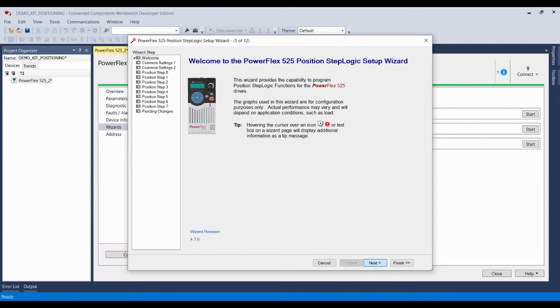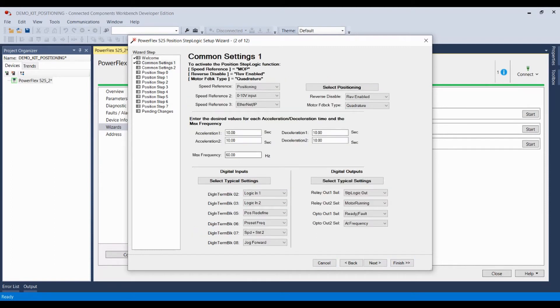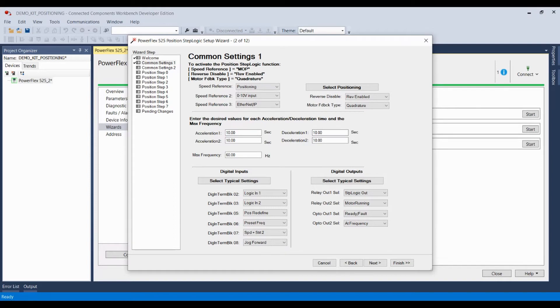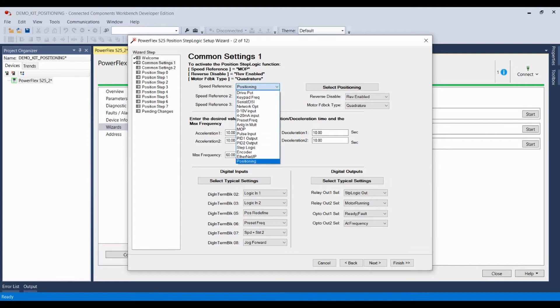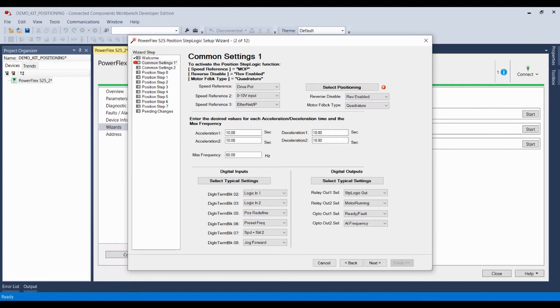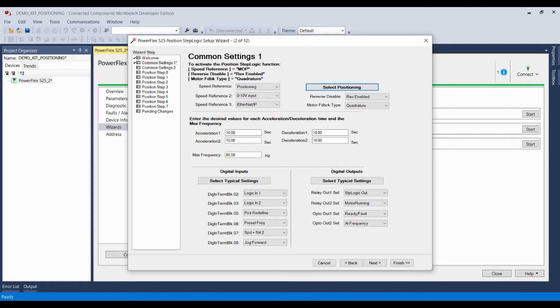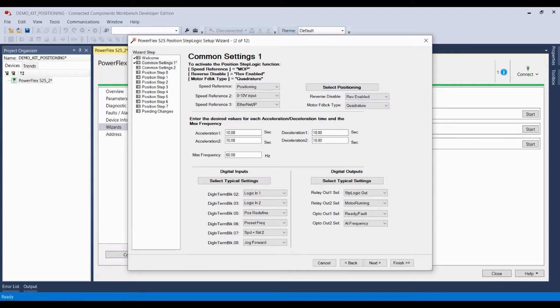After taking heed of warnings, I'm going to move into common settings one. Now, these are all the common settings you'll need to engage in order to properly set up positioning for your PowerFlex 525. If you hover over each, you'll notice that the parameter that each input setting pertains to will be listed for you, and you can always go back to parameter settings to references if you prefer. Now, first thing you'll notice is that speed reference one must be positioning. That has to be the case if you're going to engage in positioning with the drive. If that's not true, a red exclamation point will show up, letting you know that you need to press that button there and make that positioning. Speed reference two and three can be whatever speed reference you prefer, and you can use the digital input to switch between the three as needed to engage in a jog action to find home again if that's required. You can also either enable or disable reverse, depending on your process needs, and you can choose your motor feedback type.